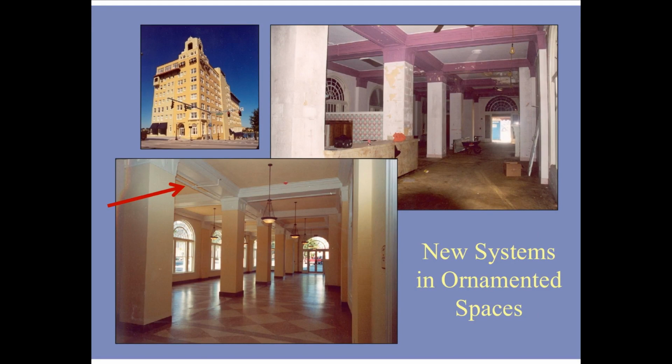A new sprinkler system was installed in this large lobby space. Note that the primary line was located close to an existing beam and on the opposite side of the column line from the main entry. Individual sprinkler heads were evenly spaced in the center of each span, with branch lines wrapping the bottom of the beam for connection to the trunk. The pipes were painted to blend in.